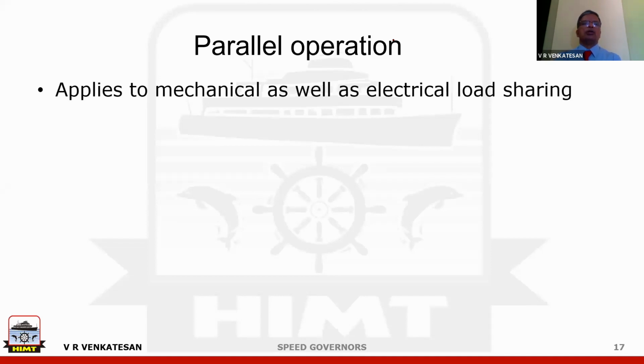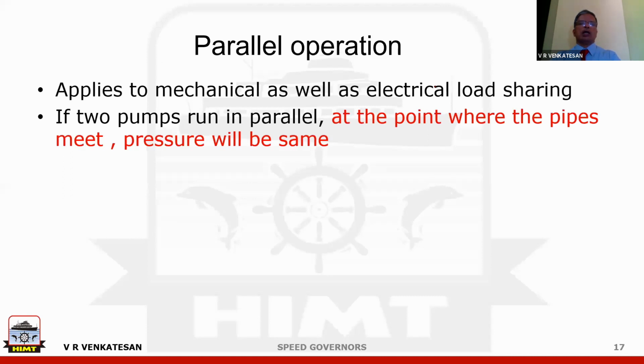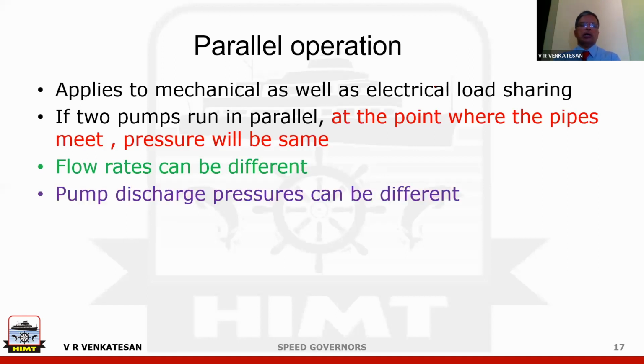Okay, but the main issue is parallel operation. So what is the meaning of parallel operation? You look at it like this. It is not related to generators alone. It applies in a lot of other systems, mechanical, electrical, and others. So if you run two pumps in parallel, will you agree that at the point where the two pipes meet, pressure must be the same? You cannot have two different pressures where the two discharge pipelines join. But the flow rates can be different. One pump can supply more liquid, the other pump can supply less liquid. But where the pipes join, it has to have the same pressure. Individual pump discharge pressure can be different, but where they join, at that point, the pressure cannot be different. You cannot have two different pressure readings at one point in a pipeline.